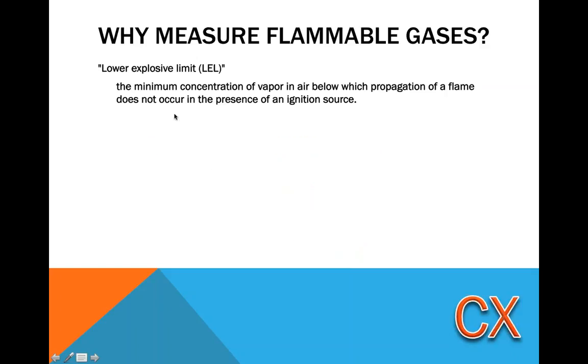Why would you want to measure flammable gases? There's something called the lower explosive limit, and that's the level which you want to detect gases to let you know if there's a situation present where an explosive situation can happen. The LEL, or lower explosive limit, is the minimum concentration of air in which a propagation of a flame cannot occur in the presence of an ignition source. So it's the most amount of gas you can have. That's the limit of gas you can have in a normal atmosphere. And again, these are normal atmospheres, which means oxygen enriched atmospheres can cause a different situation.